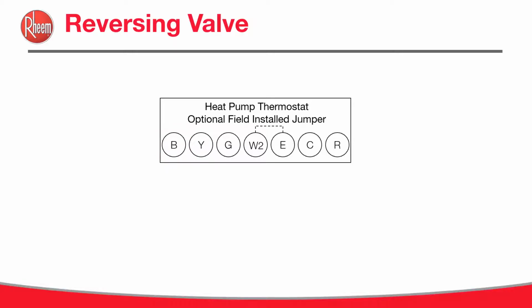Depending on whose thermostat, if you're using a generic one, then they'll have B and O terminals. So you have to remember that you're connected to the B terminal when you're hooking up to a Rheem or Ruud product. If you inadvertently connect to the O terminal on the thermostat, what will happen is when you set the unit to cooling, you'll actually be in heating mode. So if you're on a system, you've got it in cooling and it's in heating, look at those terminals, you're probably hooked up to the O terminal, right?